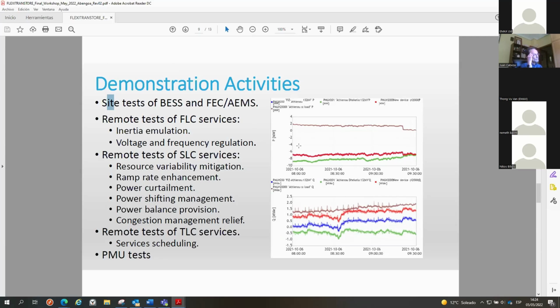The site tests were mainly devoted to verifying that the BESS was able to inject and absorb power to the grid, both in continuous mode and in fast charge/discharge mode, so we could be sure it was responding successfully to the power setpoints sent to it. Services like frequency regulation and voltage regulation were also tested on site.